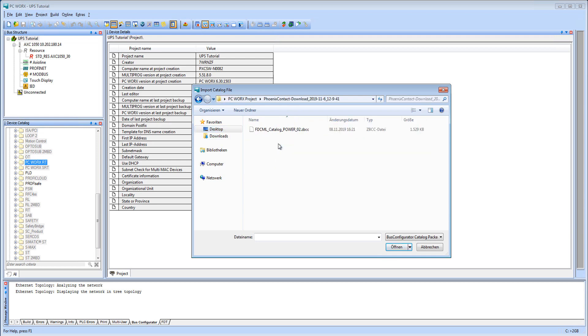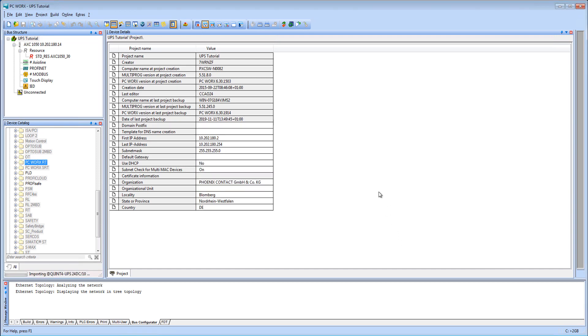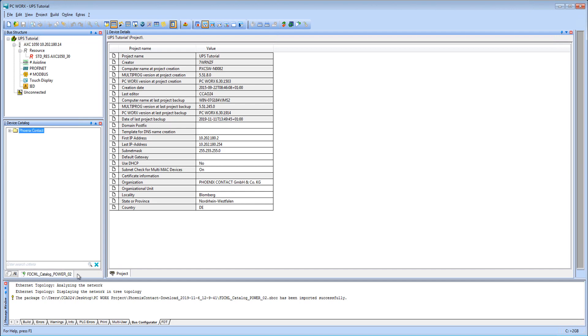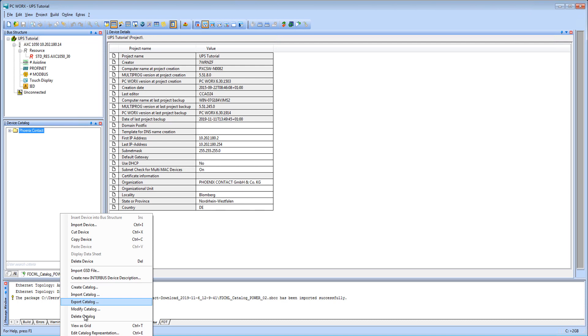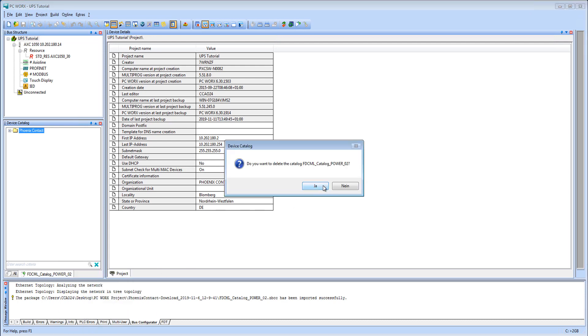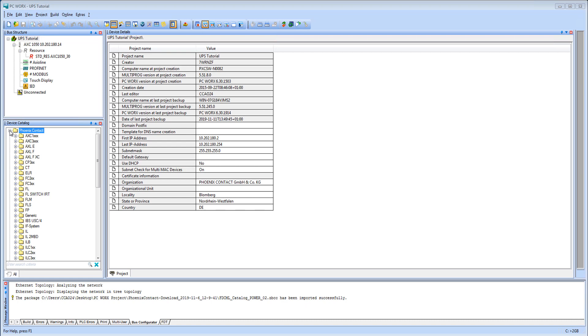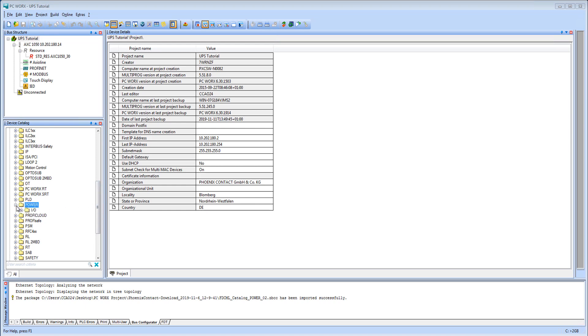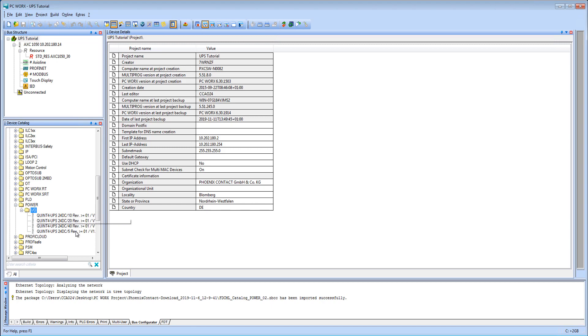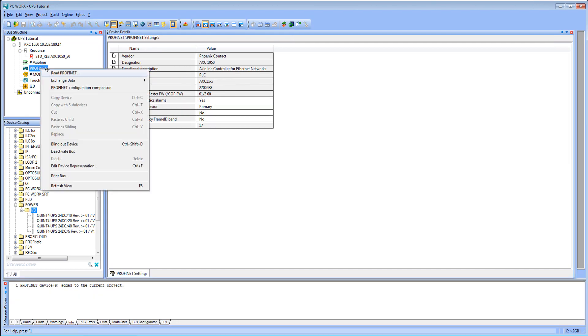Select the previously downloaded FDCML catalog and import it. The devices are now installed in the subfolder Power. Click with the right mouse button on Profinet and press Read Profinet.